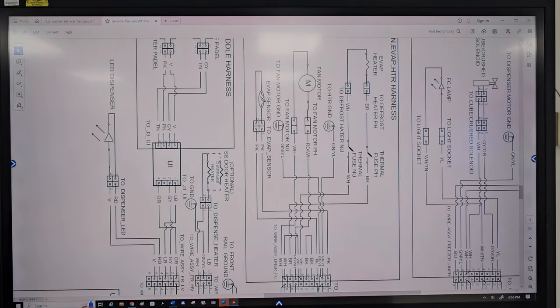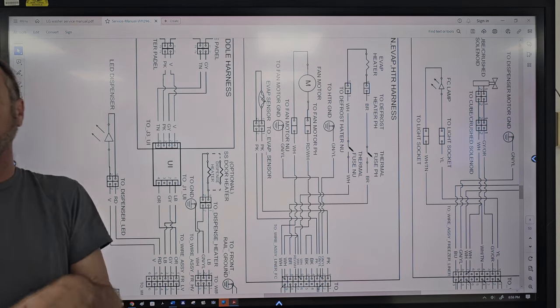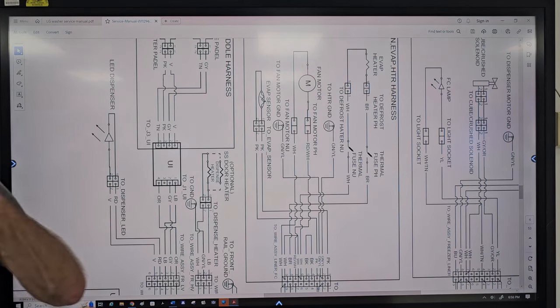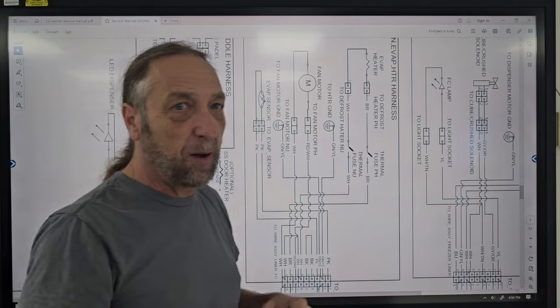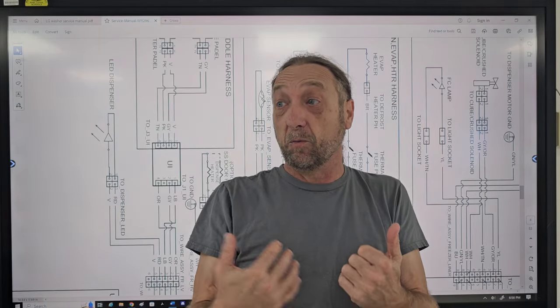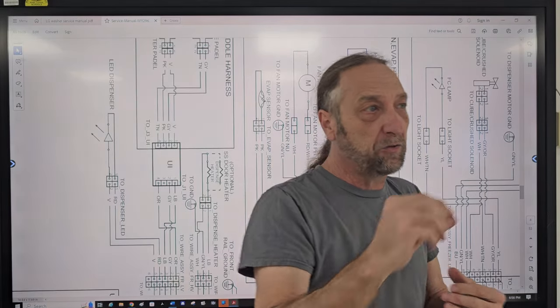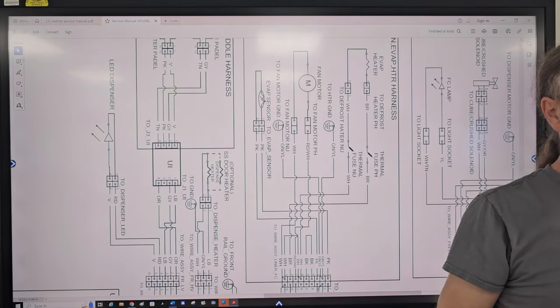The motor could be humming and still not rotating. I've seen ice makers where the fill tube splashed water over the side and a piece of ice jammed up the fan blade. We've had some service flashes, like on Frigidaire, the fan motor behind the ice maker in the refrigerator compartment, there's a little evaporator, a little fan there, and they have a shroud around the fan. And when it goes into defrost, it creates steam. And then when it touches something cold, it creates water droplets, but it's in the freezer compartment where the ice is made. And then the ice builds up there and the fan don't rotate.